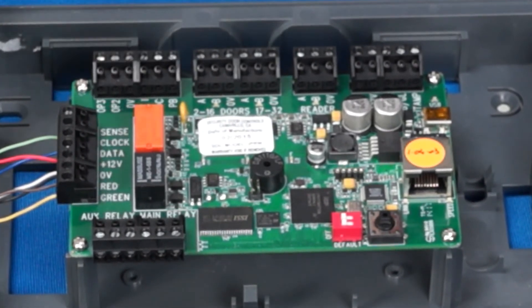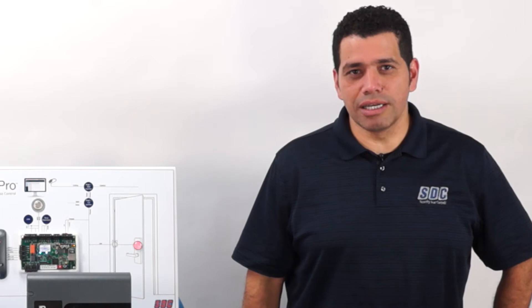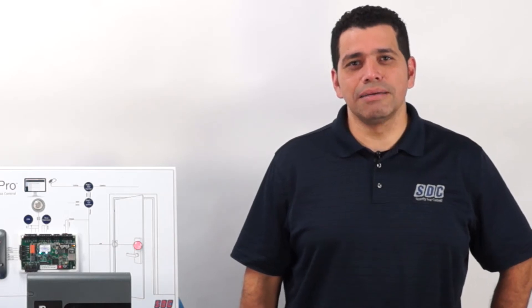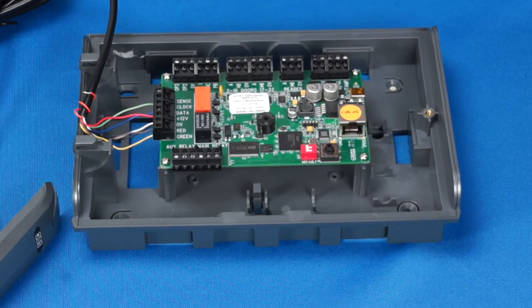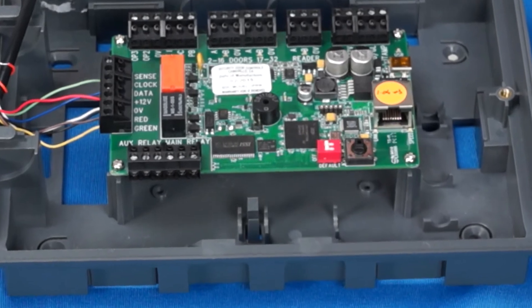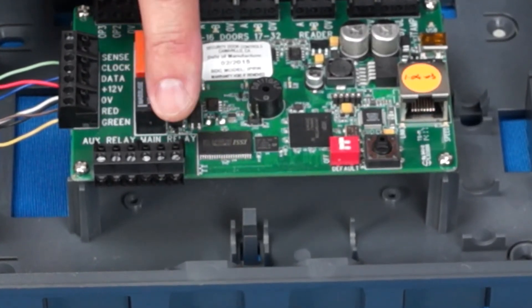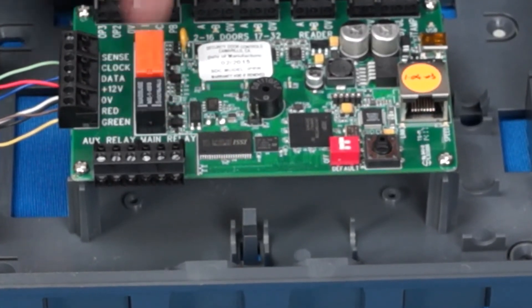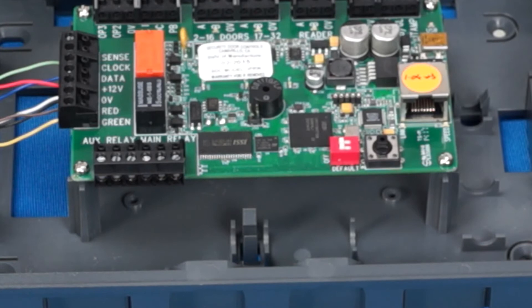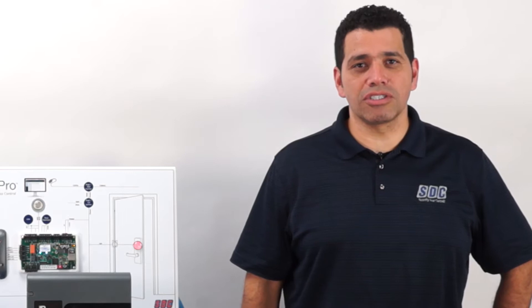Your locking device will be controlled by the lock relay whose terminals are designated main relay. The main relay is a 5-amp single pole double throw relay with common, normally open, and normally closed terminals. Refer to the installation manual for examples on how to wire a fail-safe or fail-secure lock.